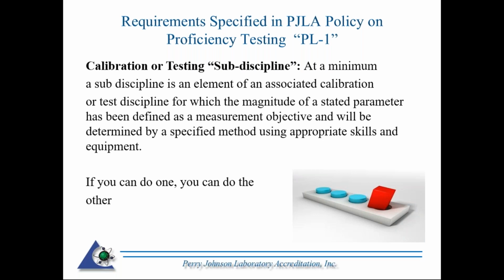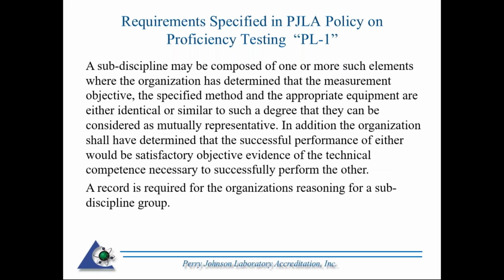So you can combine some disciplines, sub-disciplines, into combined sub-disciplines. We'll touch on that. Pretty much as I just stated, a sub-discipline may be composed of one or more elements where the organization has determined that the measured objective, the specified method, and the appropriate equipment are either identical or similar to such a degree that they can be considered mutually representative. In addition, the organization shall have determined that the successful performance of either would be satisfactory objective evidence of the technical competency necessary to successfully perform the others.